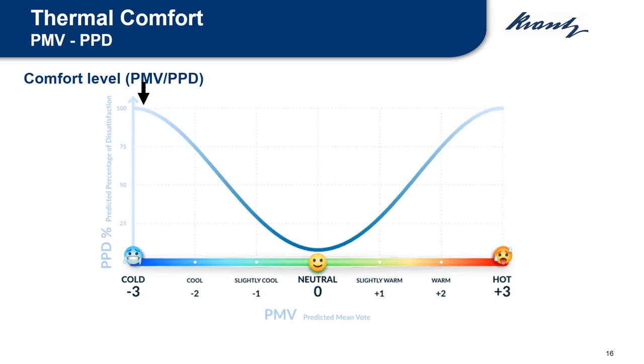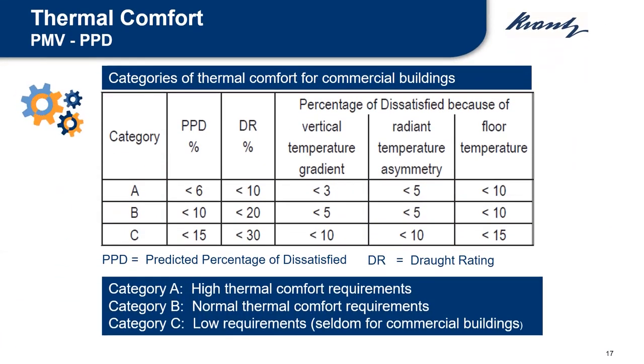Predicted percentage of dissatisfied, PPD, is an index that establishes a quantitative prediction of the percentage of thermally dissatisfied people determined from PMV. The main factors causing local discomfort or dissatisfaction may be the result of overly high indoor air velocities, draught rating DR in percent, overly high vertical temperature gradients, too much radiant temperature asymmetry, and uncomfortable floor temperatures.